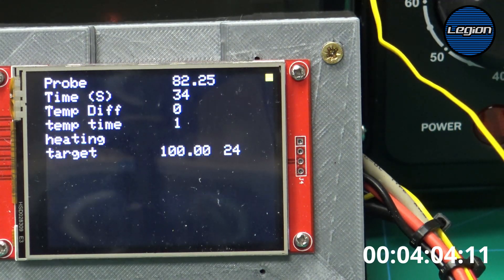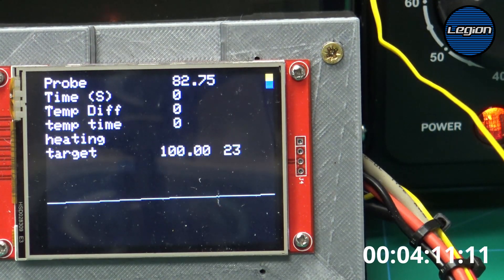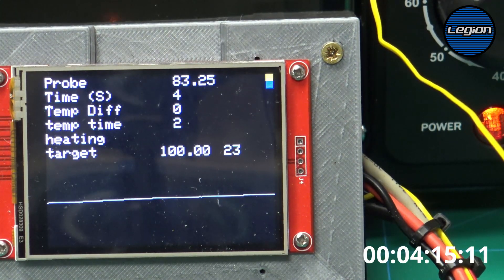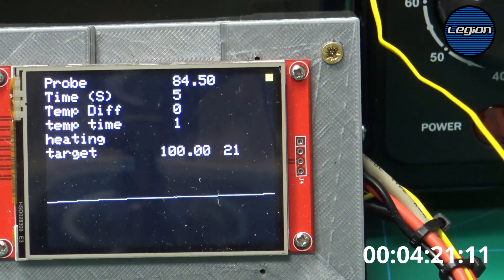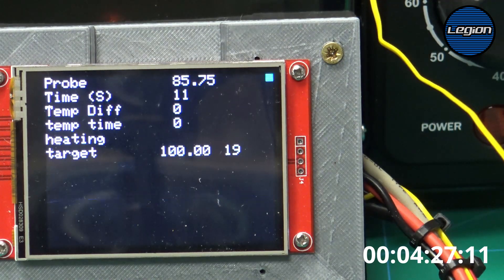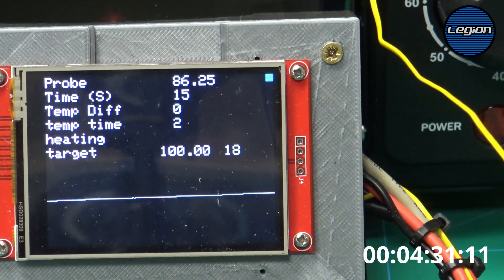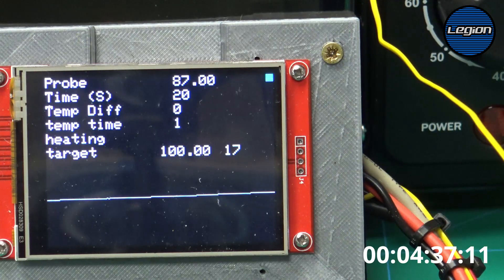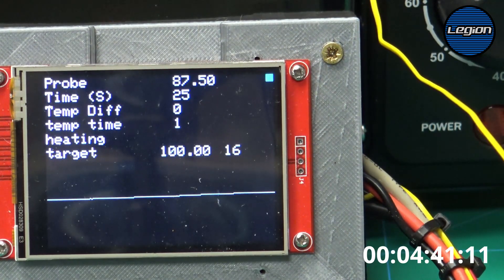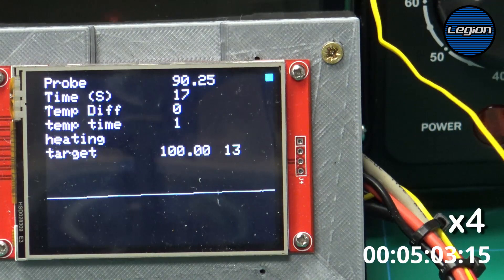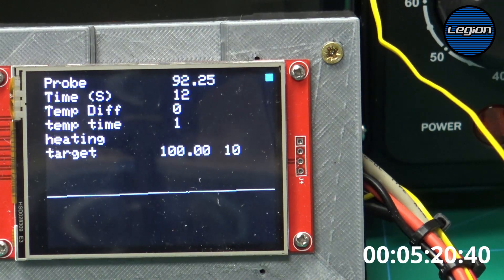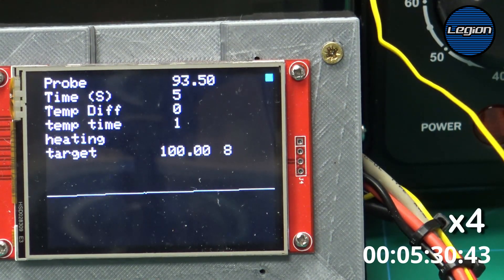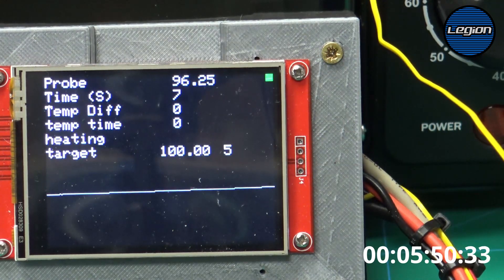So when we get to over at below 20% we should be in the lime range. So we're still heating although a bit slower. There we go the element has come on again. And note that the element stays on for a shorter period. So we're now at 20. We've gone over 20 and we're in the cyan range. So the next bracket is 5%. So we're now within 10% of our target temperature.